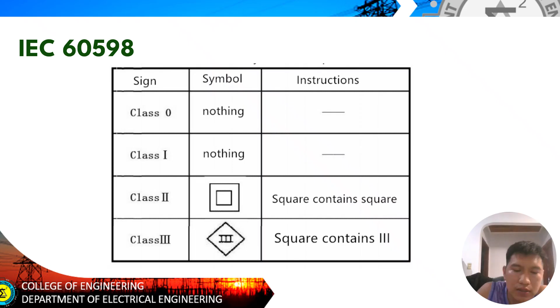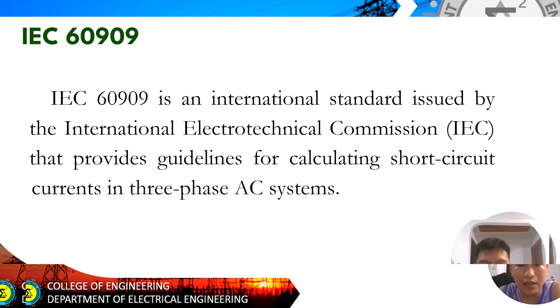IEC 60909 is an international standard issued by IEC that provides guidelines for calculating short-circuit currents in three-phase AC system. So under that, meron din pala tayong guidelines for calculating SC or short-circuit currents in three-phase system, AC system. So initial short-circuit current ay SC natin. So ito yung paano natin kukunin. So yung voltage factor natin, okay, times the nominal system voltage over square root of 3 times the total impedance of the system from the fault location to the source in ohms. So, yan yung binigay ni IEC sa atin na formula to compute that initial short circuit current natin.